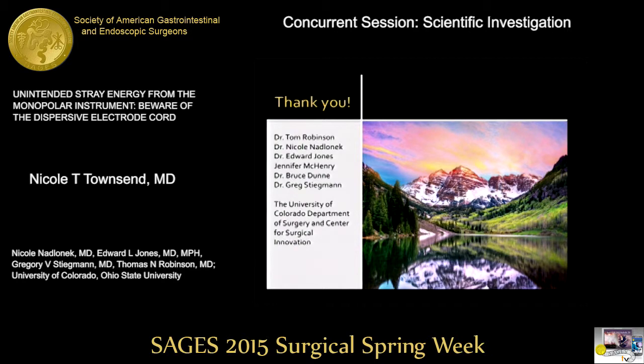Thank you for the question. So in this particular study, we didn't look at specifically a minimum amount of distance. In our previous studies looking at antenna coupling with the active electrode, about 15 centimeters of separation is usually sufficient to overcome a lot of the stray energy transfer.